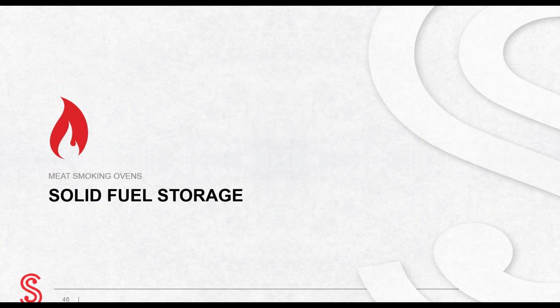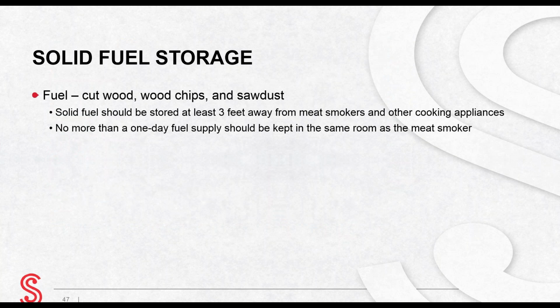We'll now discuss proper solid fuel storage. We know that meat smokers are solid fuel cooking appliances. Meat smoking often uses solid fuel like cut wood, wood chips, and sawdust. It is important to think about where you are going to store this fuel to prevent fire hazards. Solid fuel should not be stored within 3 feet of the meat smoker or any other cooking appliance. Only 1 day's supply of fuel should be kept in the same room as the meat smoker cooking appliance per NFPA 96 Chapter 14.